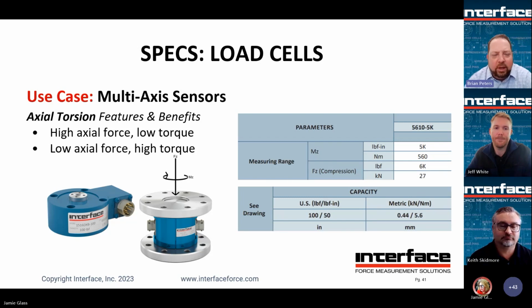Yeah, some of that's going to be a function of how the sensor originally started. So the unit on the left, out of the 1500, started as an axial load cell, and we added some additional bridge on there for torsional measurement, whereas the one on the right started as a torque cell. So for similar capacities, it's going to be shifted much higher on the torque side, with maybe less sensitivity in the axial mode, for example. So it's just good to pay attention to how the different capacities in the multi-axis line up. And we usually have a solution that'll get what's needed. So don't hesitate to reach out and ask on that.